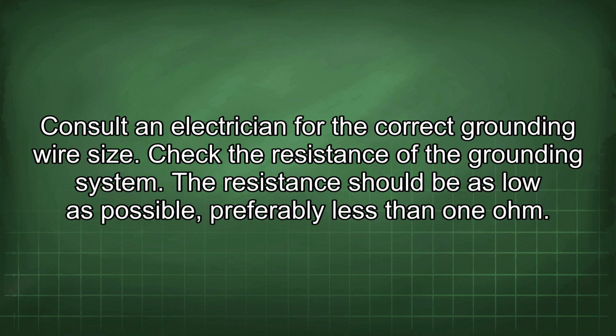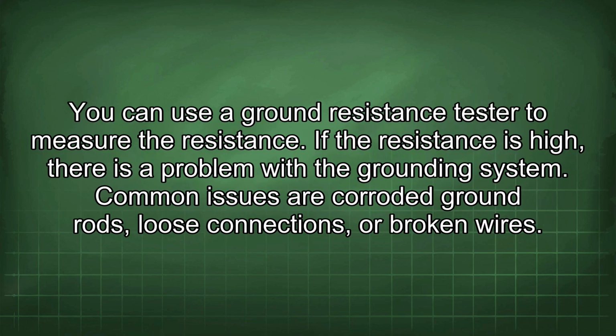Check the resistance of the grounding system. The resistance should be as low as possible, preferably less than 1 ohm. You can use a ground resistance tester to measure the resistance. If the resistance is high, there is a problem with the grounding system. Common issues are corroded ground rods, loose connections, or broken wires.